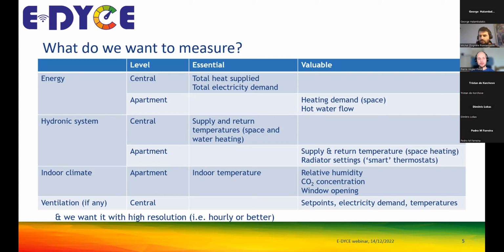When it comes to the hydronic system, the hot water supply within the building, we want to know return and supply temperatures for both space and water heating, to identify specific faults that might be happening, and also potential optimization of the different set points being used.